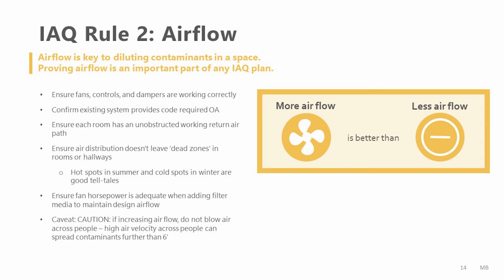Another big one, we've seen recommendations of increasing filtration. If you have MERV 8 filters, take it up to MERV 13 or even higher filters if they fit into the slots. Of course, if you increase your filtration and you increase your pressure drop, you can actually reduce the airflow that you're delivering from a system, and that takes us back to rule 1. More airflow is better than less airflow, and more outdoor air is better than less outdoor air. So make sure that your fan is sized for the filters that you're putting into your system.